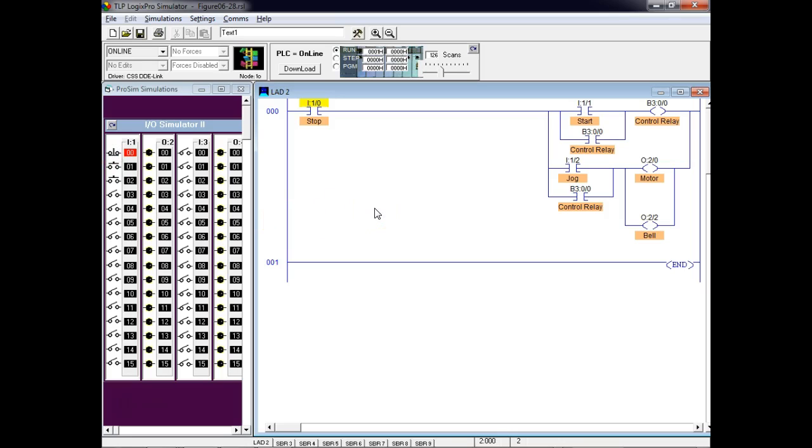Now it's true. And this is what gets people in motor controls totally confused, because they get that dang thing with an arrow through it. They say, well, that's a normally closed push button. It is in motor controls. In PLCs, it's an examine if open. So this is an examine if closed instruction. So look, it's true now.